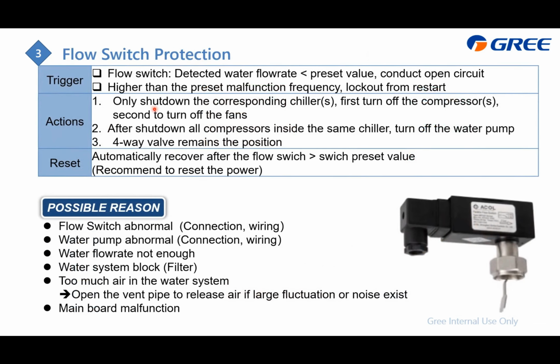Next, we will go to the flow switch protection. This is only triggered by the flow switch when the detected water flow rate is less than the preset value. The preset value is different for different models. Of course, we conduct the open circuit, just like a switch. And here are the actions that we will take when we see the open circuit signal.